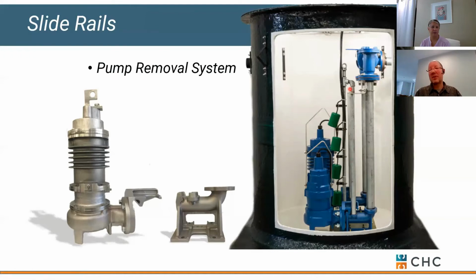Now you can center it and get it out of your basin and take it off for service. Okay, that's how a removal system works. One thing I should note about pump selection: each pump in a typical commercial sump and sewage setup is designed for 100% service. So you've got full backup, or full redundancy, inside a basin. Here we're showing different size pumps, but that's very unusual.